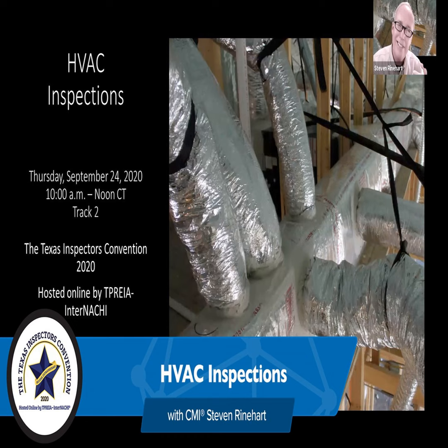And really an amp meter probably would have to tell you that, because you can look on the unit. It tells you how much each one of them pulls. They say, okay, all 3 of them are working with 15,000, there's 5,000 watt elements in here, and this unit's only pulling 5,000 watts.